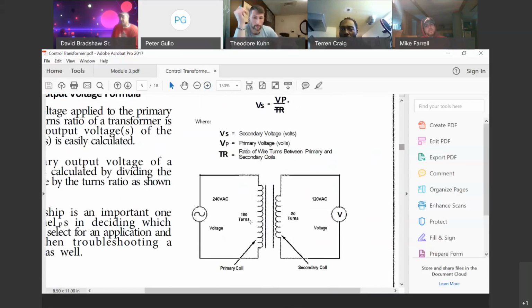The primary always goes on top, the secondary goes on the bottom. So if the primary is 100 and the secondary is 50, we got 100 over 50, we can break that down to 10 over 5. And 5 goes into 10 two times. So this would be a step-down transformer, 2-to-1.